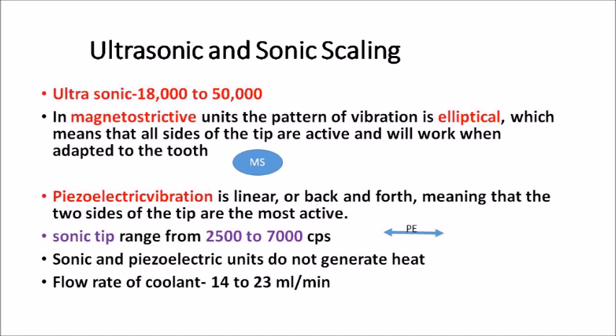Then sonic. Sonic tip ranges from 2500 to 7000 cycles per second. Now sonic and piezoelectric ultrasonic do not generate heat. Heat production is usually seen in magnetostrictive ultrasonic units. But sonic and piezoelectric units use a coolant. Why is this coolant used? To flush off the dislodged calculus and debris. And the flow rate of the coolant, this is an important question, is 14 to 23 milliliters per minute. Mind, 14 to 23 milliliters per minute.